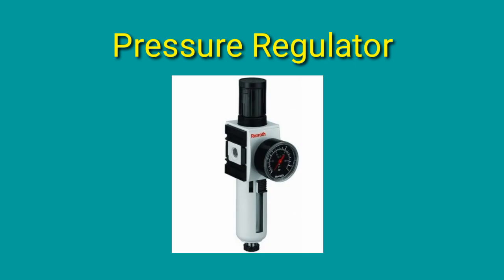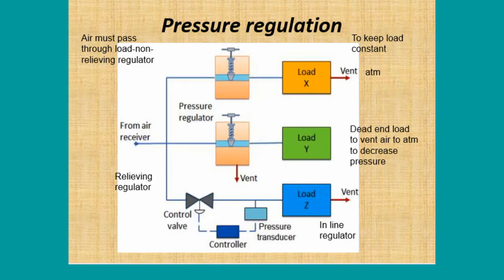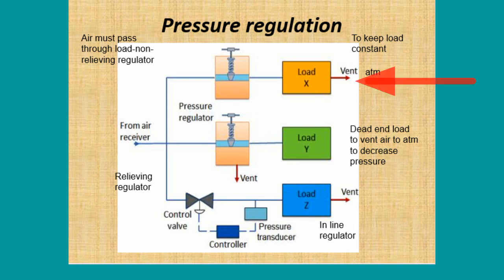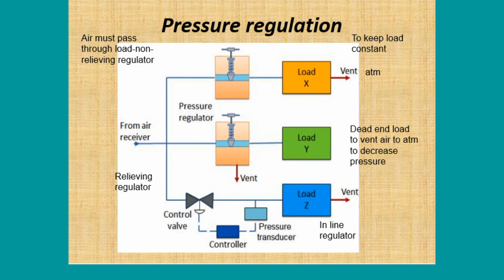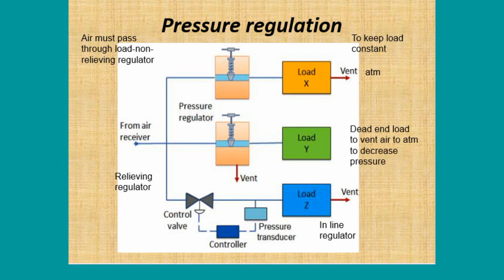The pressure regulator, or air regulator, is one of the most important parts of a pneumatic system. In the first type, the load continuously vents air to the atmosphere, and the pressure regulator restricts air flow to the load to control pressure. Some minimum flow is required to operate this regulator. If the load is a dead-end type that draws no air, pressure in the receiver rises to manifold pressure — this is called a non-relieving regulator. In the second type, the load is a dead-end but the regulator itself vents air to atmosphere to reduce pressure — this is called a relieving regulator.